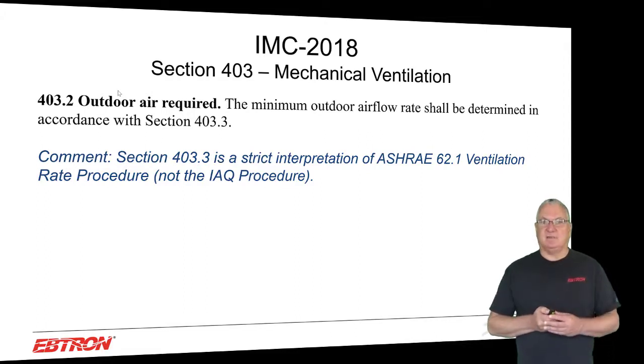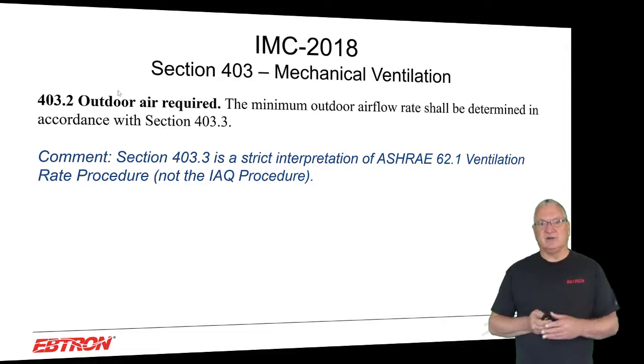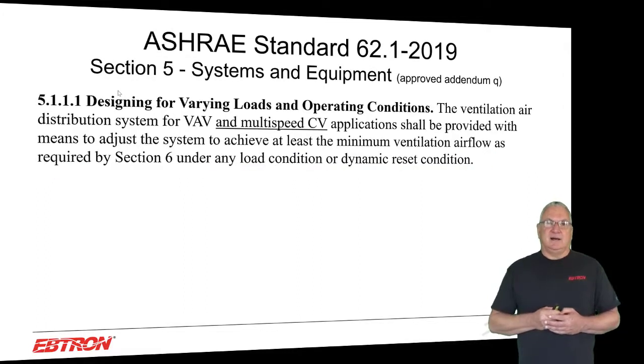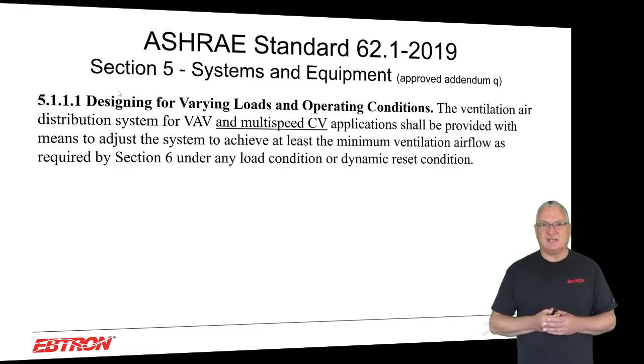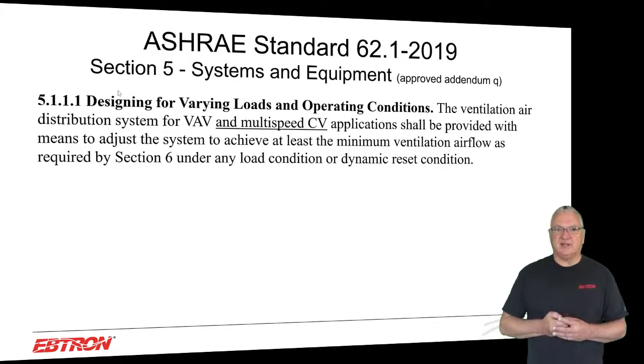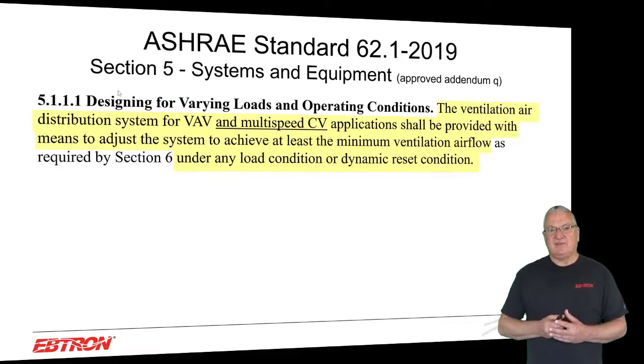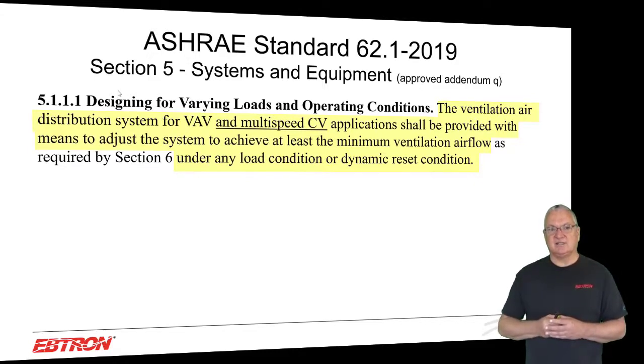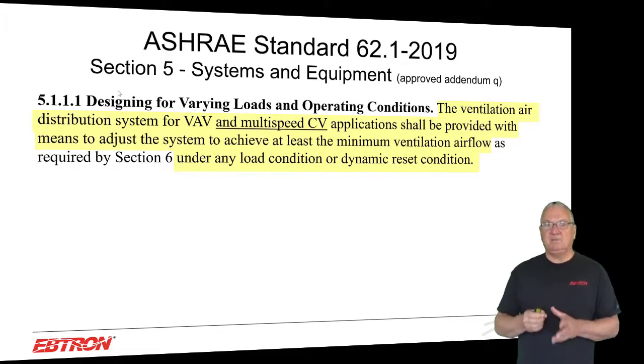I want to make sure everybody understands that, because I have people saying they don't care about Standard 62. Well, you should care about Standard 62 because it's really what your code is based on. Within the last several years, Addendum Q approved one significant change. The ventilation air distribution for VAV and multi-speed constant volume applications shall be provided with means to adjust the system to achieve at least the minimum ventilation airflow under any load condition or dynamic reset condition. It had always only been VAV.